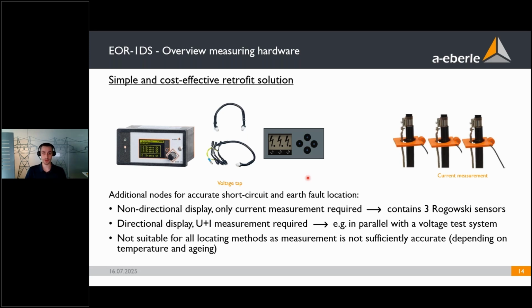But the disadvantage of using this retrofit solution is that it is not suitable for all locating methods, as this measurement is not sufficiently accurate. But it really depends on the localization method that you want to use, and of course on temperature and aging of your sensors. This is mainly used as a retrofit solution because you do not have to perform additional installation, and it's really easy to install as a retrofit, as you can see here.